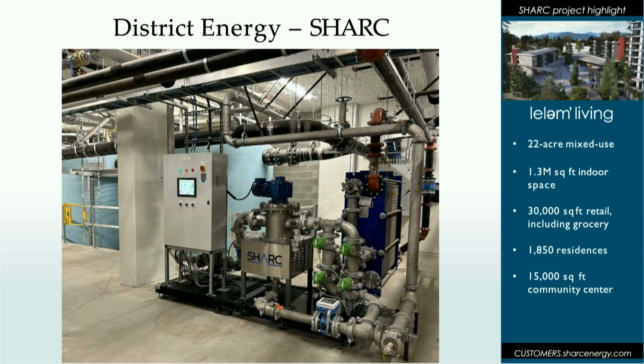Instead of cooling towers, boilers, and fluid coolers on these buildings, this is the mechanical room. These buildings pull off an ATL, an ambient temperature loop, with water provided at a minimum of 66 degrees and a maximum of 77 or 78 degrees year-round. Every building has water source heat pumps or water-cooled refrigeration for supermarkets and convenience stores, and they're also doing some snow melt on site.